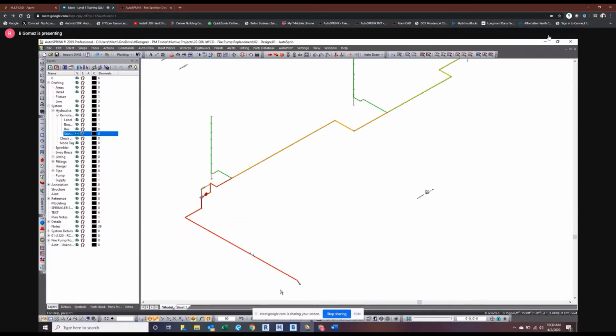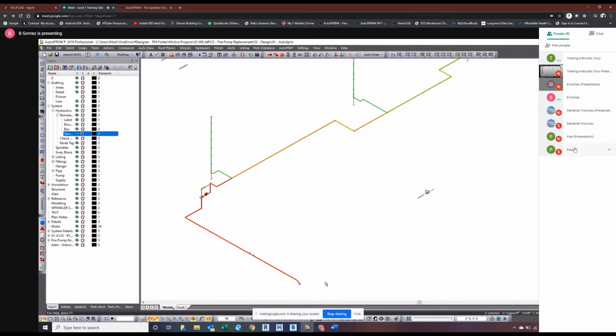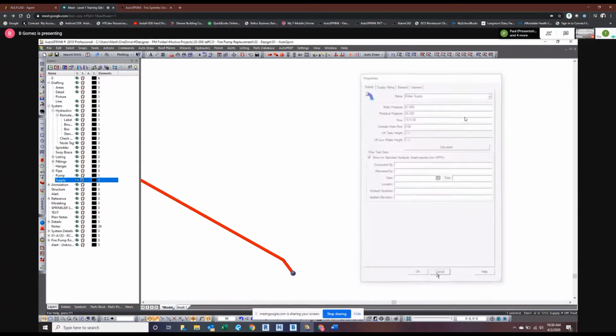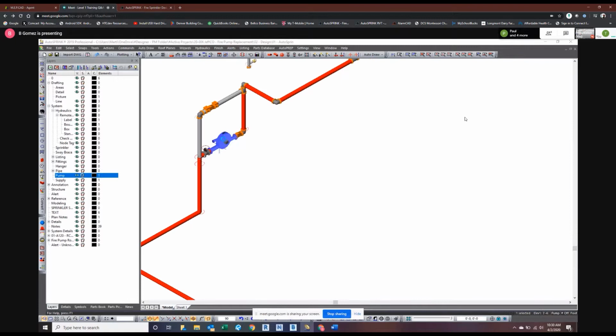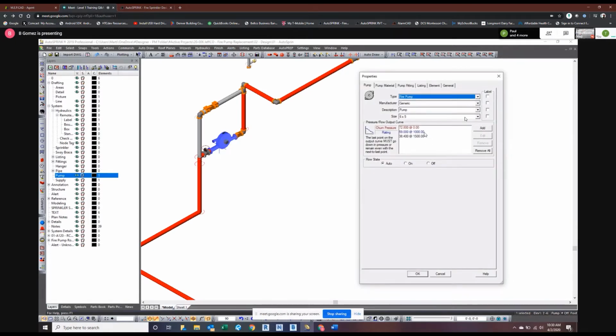Sure thing, man. The next question was, I was dealing with Fred and Chuck, and the static here for the city is 67, 55 residual. The pump that he spec'd out, we're flowing at 1,000 GPM.